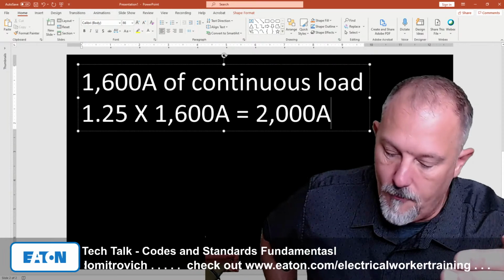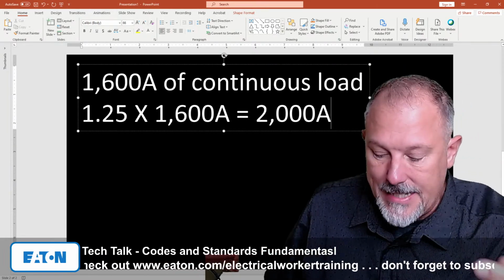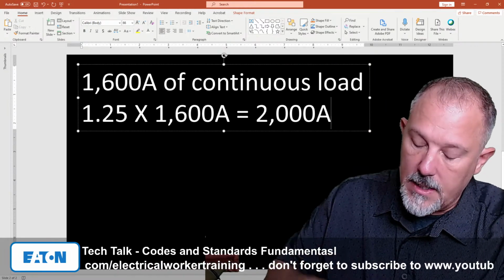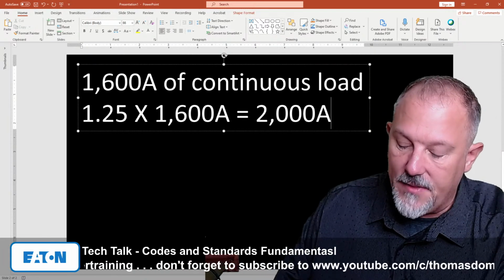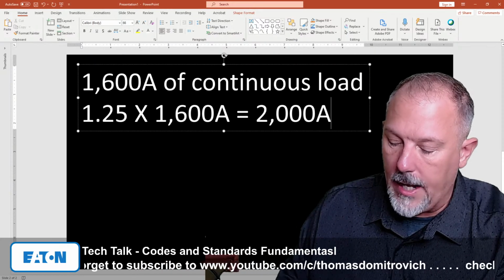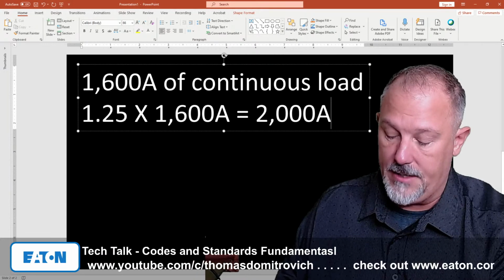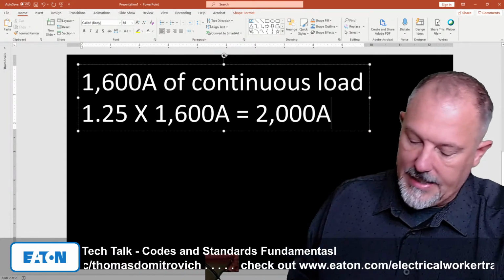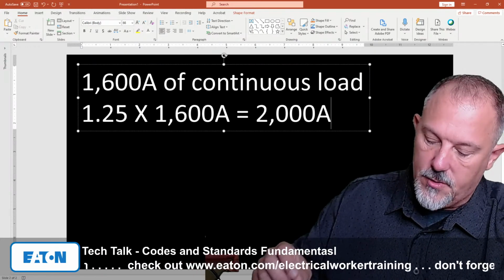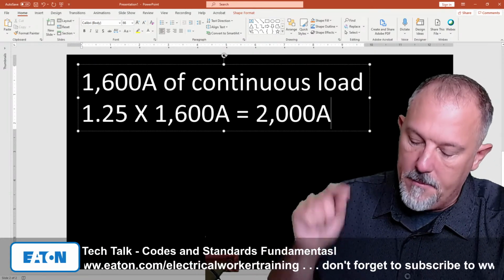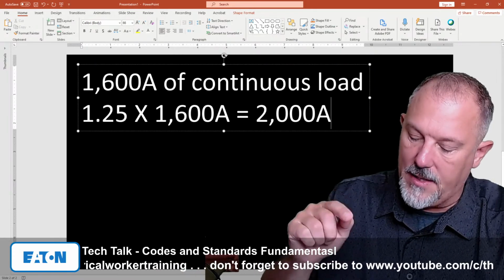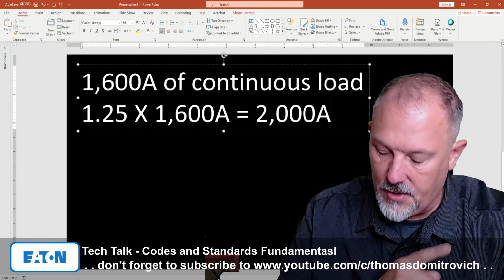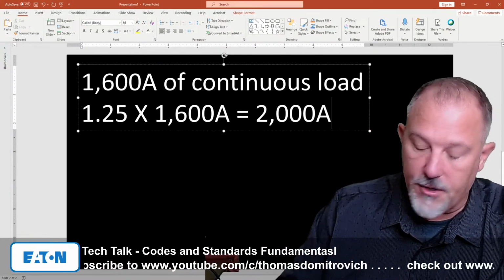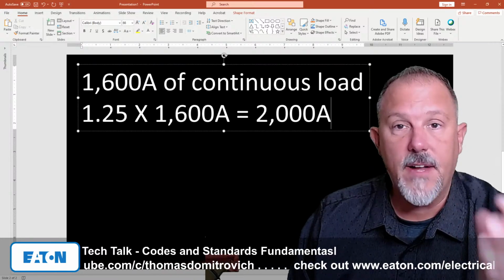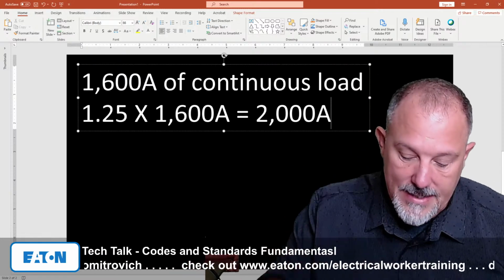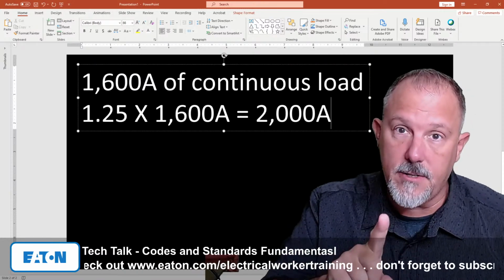In 210.19 I do two calculations. The first one is in 210.19(A), branch circuits not more than 600 volts. A branch circuit shall have an ampacity not less than the larger of 210.19(A)(1)(a) or (A)(1)(b). So I have to do two calculations. (A)(1)(a) says I have to include the 125%. Where a branch circuit supplies continuous loads or any combination of continuous and non-continuous loads, the minimum branch circuit conductor size shall have an ampacity not less than the non-continuous plus 125% of the continuous. So if it was 1600 amps worth of continuous, I would take 1600 times 1.25, come up with 2000 amps, go to 310.16, and pick my conductor for 2000 amps, which is 5 600 kcmil conductors.